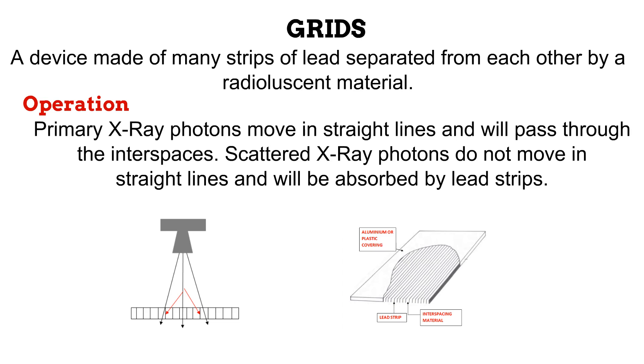Observe this on the diagram. While the black primary photons easily pass through the interspacing material, the red scattered photons are not moving straight and are absorbed by the lead strips. This is the basic manner by which grids function.